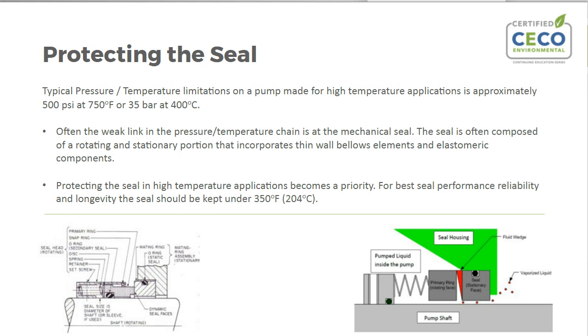Down at the bottom, I give just a quick diagram. On the right side is the basics of how a seal works. The seal basically breaks down high pressure through a very tight tolerance of very flat faces, one rotating, one stationary, of course. And within that cross section, it breaks down the pressure until it cannot flow. There's no differential pressure to release it from the pump. You can, however, get vapors and whatnot that come through the seal. So it's not a perfect seal, I guess, is the way it should be explained. It's never a perfect seal. On the left-hand side, I just pinpoint some of the different nomenclature used in describing a seal and whatnot.